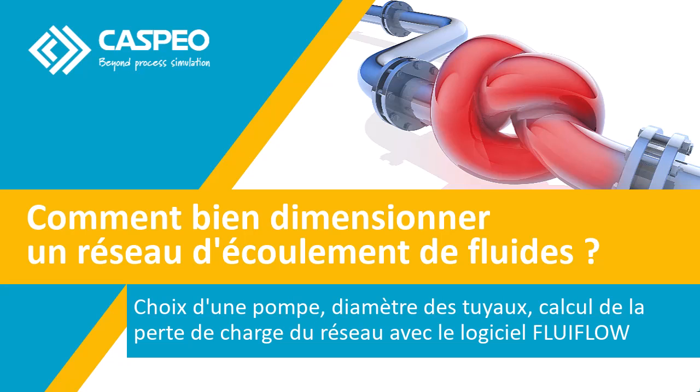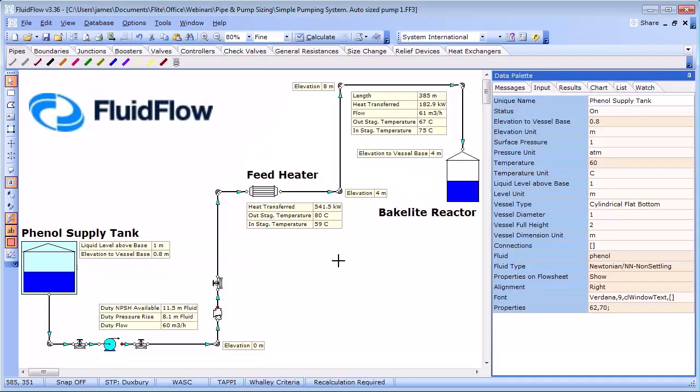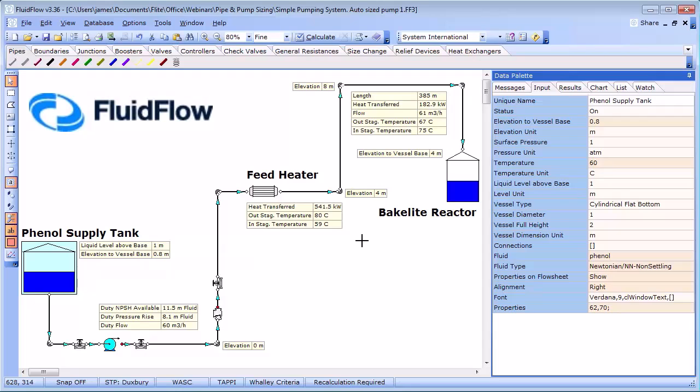So in today's session we are going to look at using a systems design approach to size our pipework and circulating pump. By systems design approach we mean considering all elements or components in the system connected together. This allows us to consider components interaction in the system. Using spreadsheets or hand calculations consider elements in isolation and this is unlikely to provide you with an optimal or flexible design solution. Adopting a systems design approach is therefore key to understanding the true performance of the system.